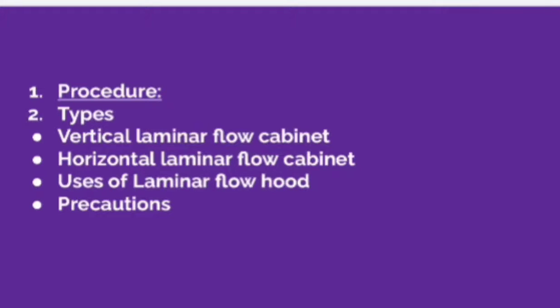In this type of laminar airflow cabinet, the air moves from the top of the cabinet directly towards the bottom of the cabinet. A vertical airflow working bench does not require as much depth and floor space as a horizontal airflow hood, which makes it more manageable and decreases the chances of airflow obstruction or movement of contaminated air downstream.